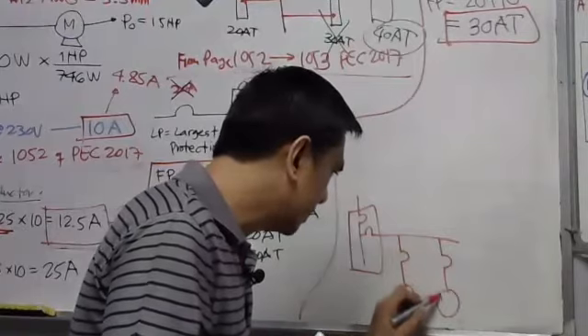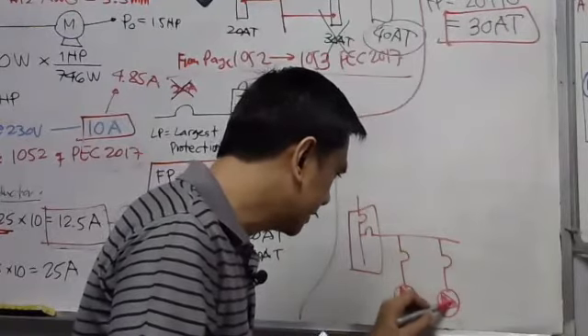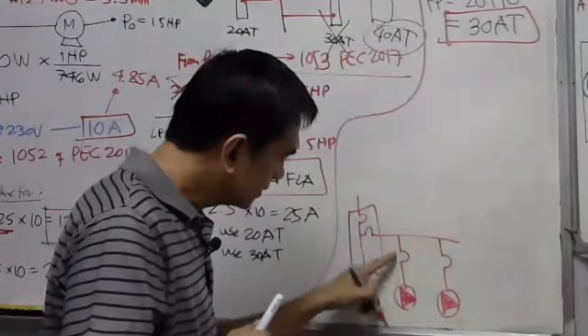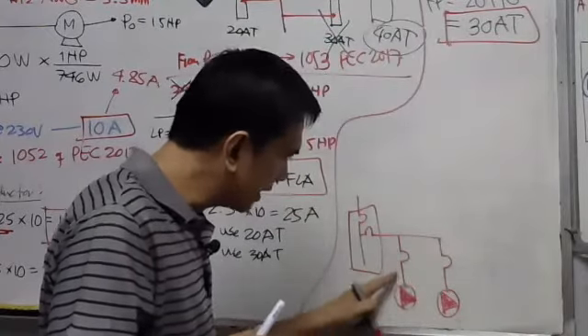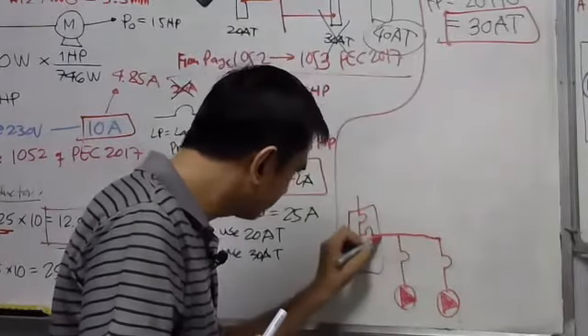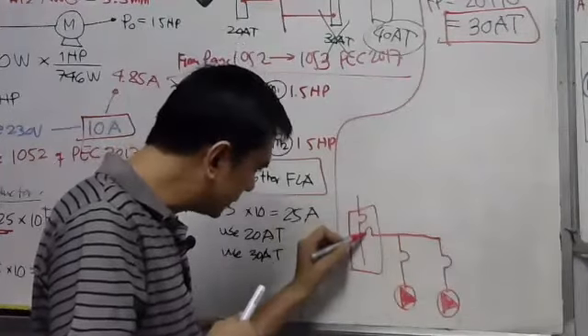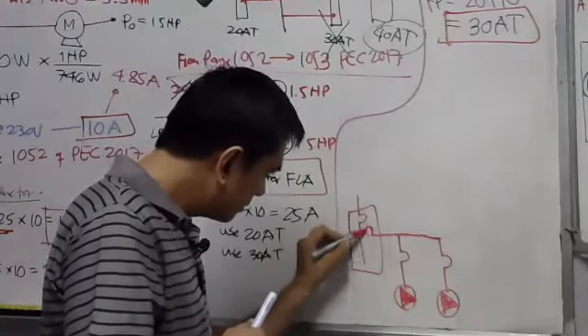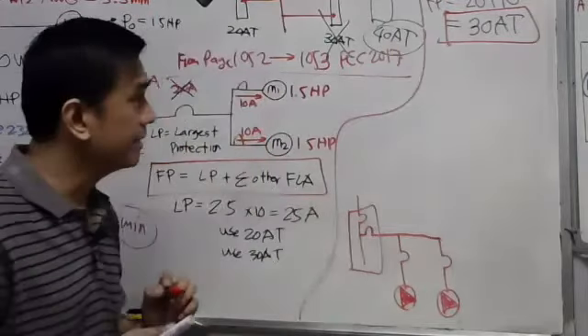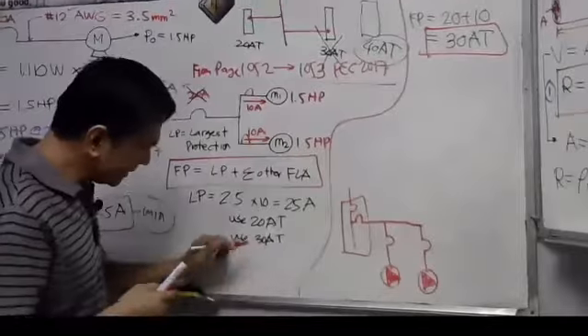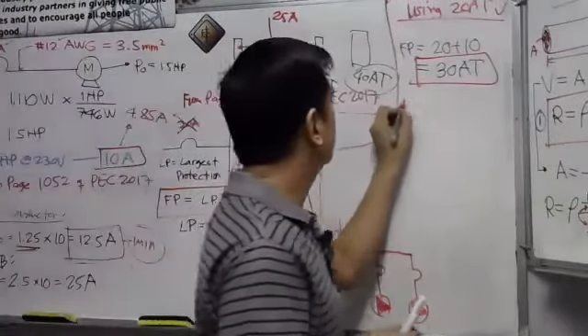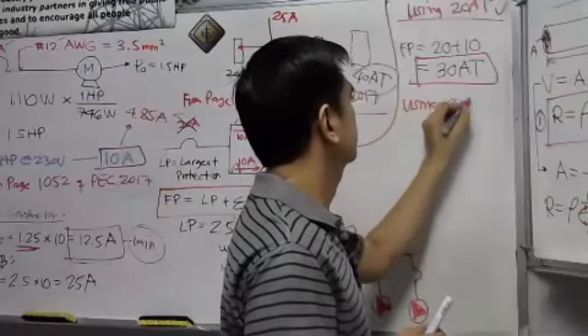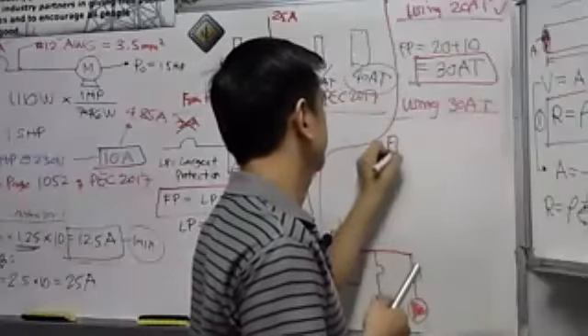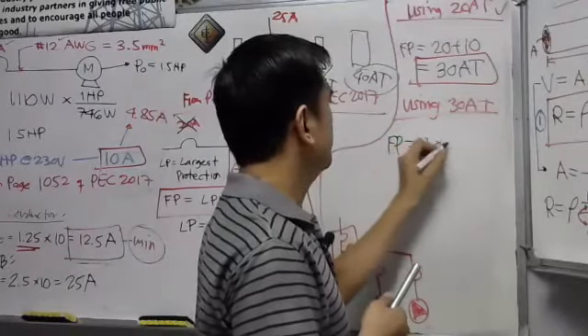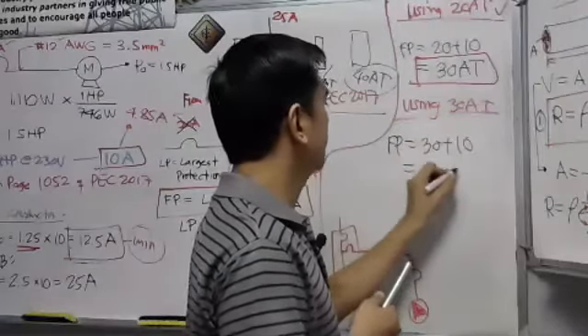So there are two air conditioners here. You will see there is an individual circuit breaker and branch circuit conductor here, but they have a feeder. This is a feeder conductor. This is the feeder breaker. That is the feeder breaker. If we use the 30 ampere here, using the 30 ampere trip, what is the feeder protection? We use 30 plus 10, so we will use 40 ampere trip.